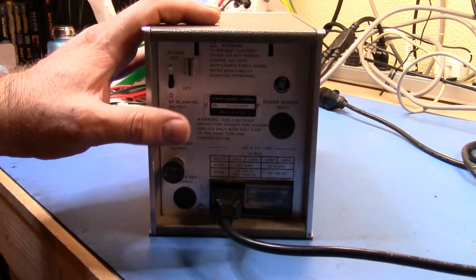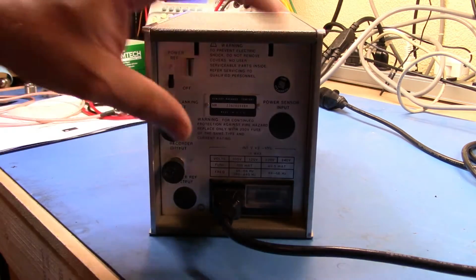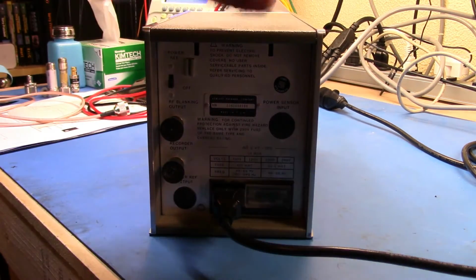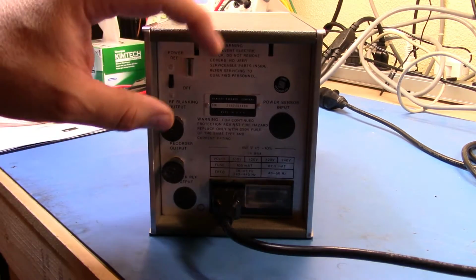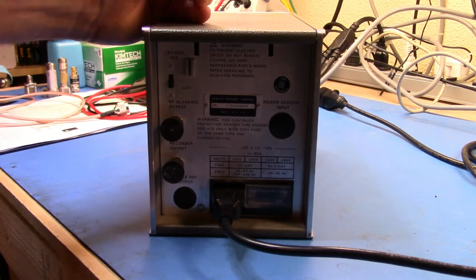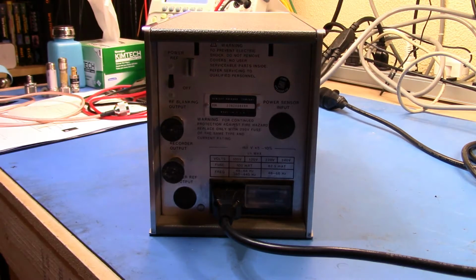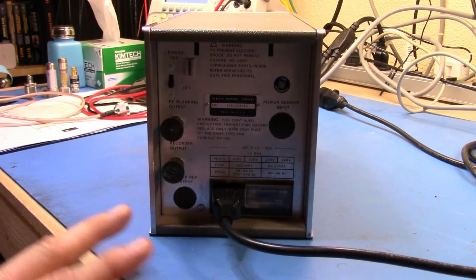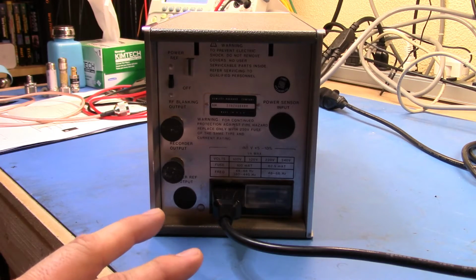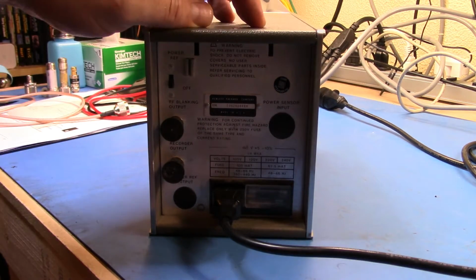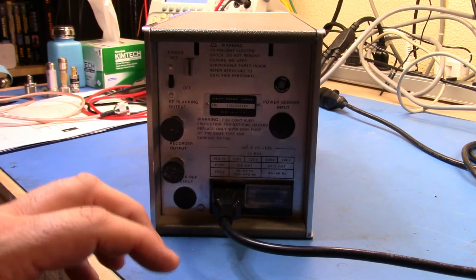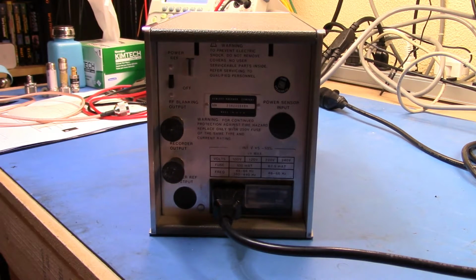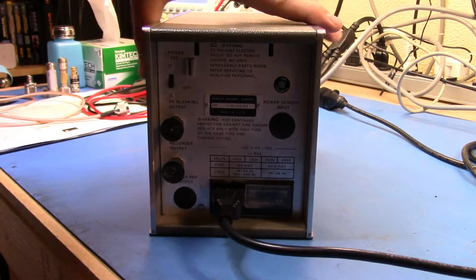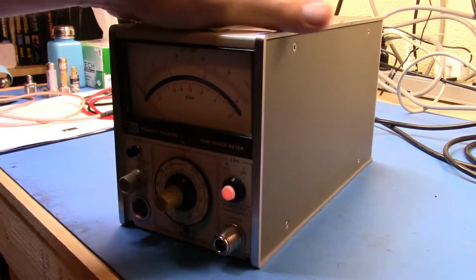You could have it in the back of the unit, and you would do that in conjunction with the RF blanking output normally in a production or rack mount world, because what the RF blanking output does is, when you press the 0 key, you get a signal out here which enables you to automatically disconnect the RF signal that's coming into the unit during the zeroing process. So you don't want the signal input or a live signal being read when you zero. So you can automatically turn that off, and it makes for the process much better.